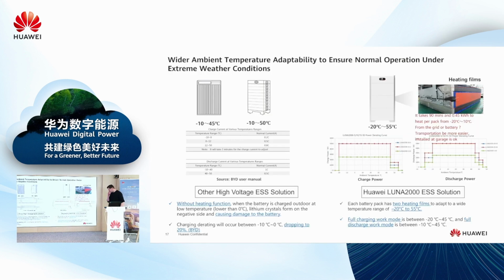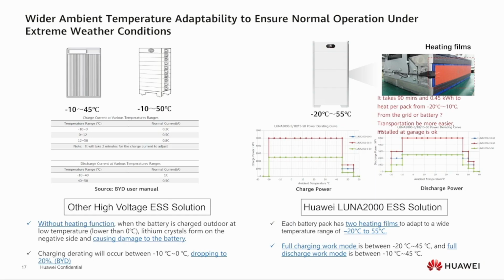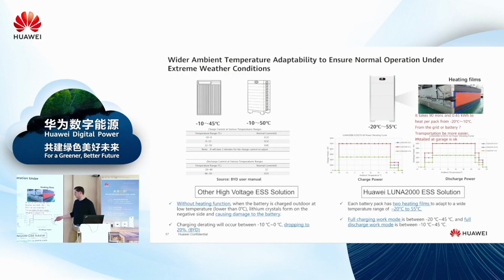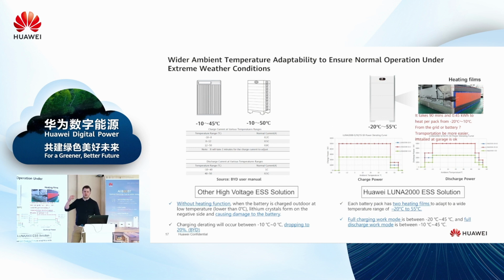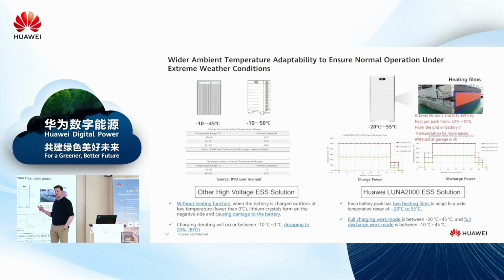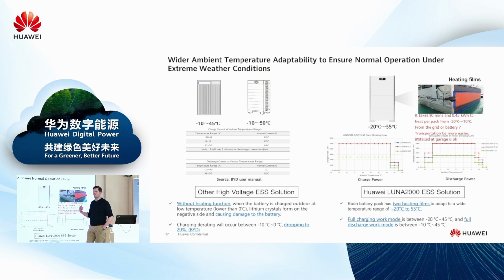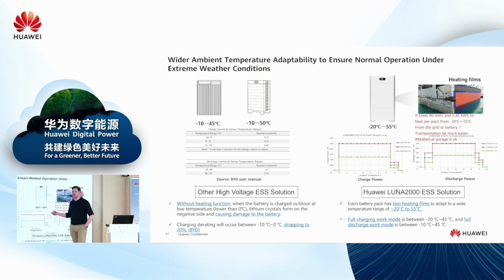So the working temperature is around between minus 20 up to 50. But of course, the temperature is affecting the energy storage system and there is no way around it. The Huawei battery has a built-in side heater. So when you just mount it outside and your temperature is below minus 10 degrees - because this is the temperature where the battery itself starts to operate normally - it will heat up the battery up to minus 10 degrees using power from the grid. This is the power you have to import from the grid. And then after, it will start to operate normally. So there are some heating mats inside.